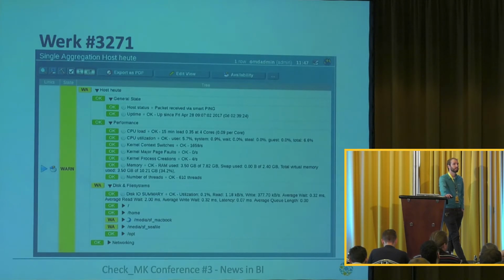And then you calculate the whole thing, and if it's critical on top, then it is a downtime. So to say it differently, let's assume that everything where you have maintenance is really broken, and everything else does work. If the application still works, because the components are redundant, then it really doesn't need a downtime. But if it doesn't work anymore, then you do see the downtime symbol up there. So the downtime symbol tells you, okay, warning, it might be green right now, but somebody's working on that. It could turn red at any point in time because there's maintenance being done.